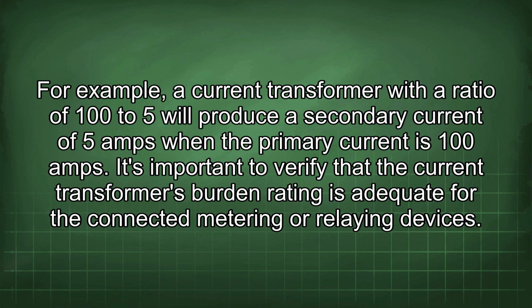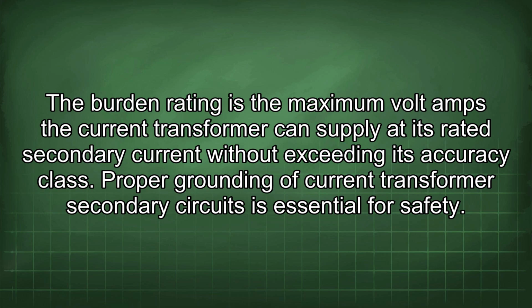It's important to verify that the current transformer's burden rating is adequate for the connected metering or relaying devices. The burden rating is the maximum volt amps the current transformer can supply at its rated secondary current without exceeding its accuracy class. Proper grounding of current transformer secondary circuits is essential for safety.